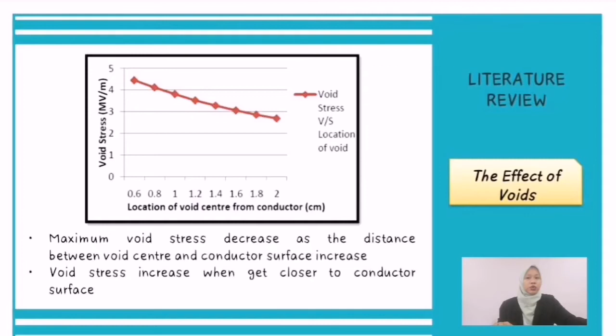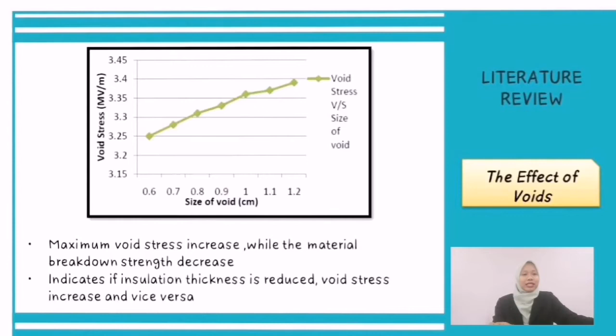So, for the size of void, the insulation material used is cross-linked polyethylene, which is XLPE, with a relative permittivity of 2.5 considered. In that situation, the maximum void stress is 3.25 MV per meter when the void size is 0.6 cm. The result shows that as the diameter of the void rises, the maximum void stress increases, while the material breakdown strength will decrease. It also indicates if insulation thickness is reduced, void stress increases and vice versa.